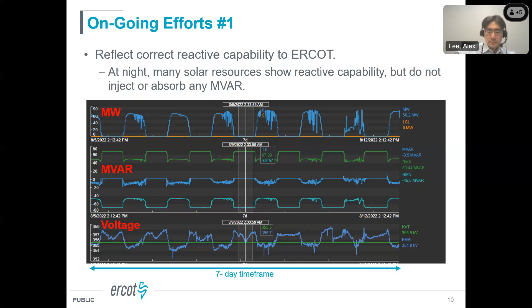In the middle pane, the middle line shows the actual megavar output from the solar resource, and the maximum or upper and lower reactive capability of that resource is shown in green and turquoise. What we can notice here is that whenever there's 0 megawatt output in between actual megawatt output, we see a flat lining of the megavar response, not responding at all, although the voltage in the bottom pane shows changes throughout the time.